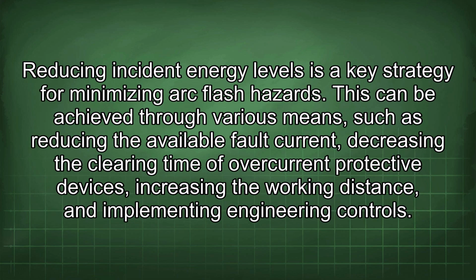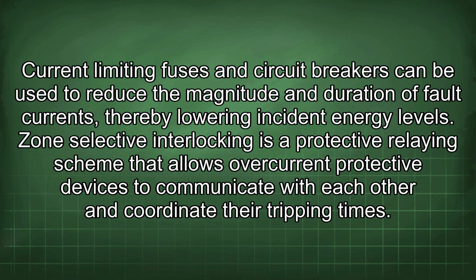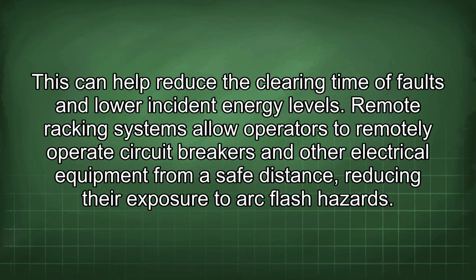Reducing incident energy levels is a key strategy for minimizing arc flash hazards. This can be achieved through various means, such as reducing the available fault current, decreasing the clearing time of overcurrent protective devices, increasing the working distance, and implementing engineering controls. Current limiting fuses and circuit breakers can be used to reduce the magnitude and duration of fault currents, thereby lowering incident energy levels. Zone selective interlocking is a protective relaying scheme that allows overcurrent protective devices to communicate with each other and coordinate their tripping times. This can help reduce the clearing time of faults and lower incident energy levels.